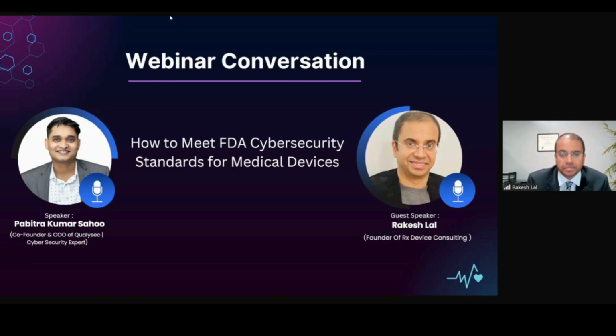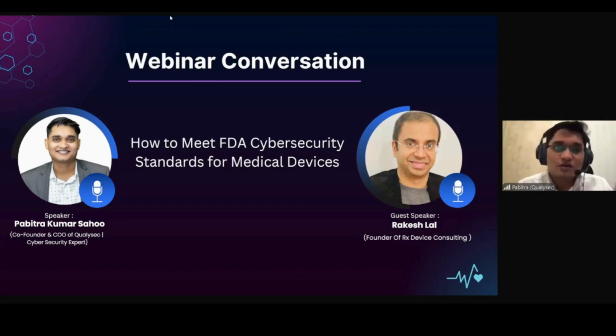Great, great. You have also added this point about inadequate testing, right? So this is the exact point. We have helped more than 10 clients of ours achieve FDA clearance. The most common reason I see, during our information gathering and discovery call, is that they just provide a scanning report, and FDA asks whether they actually tested those cybersecurity controls or not. Then they come to know that we have to do a very comprehensive test rather than just a scan using any tool.